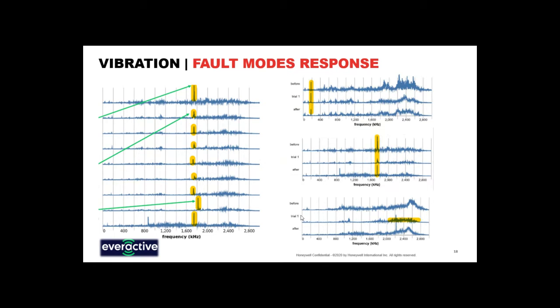What we've got on the left, starting at the top, is the baseline, so that's a healthy regulator. Through our exhaustive global database, and these things are prolifically installed in vast numbers around the world, we created the following: starting at the top, known popular Pareto type failures in the field. The following traces after the top one, 1 through 7 down, they're all following the Pareto classical fails we've noted in our historical database, and we've simulated them to see the response. On the bottom trend, we've gone back to baseline, because it's always good with any testing to start with base and finish with base.